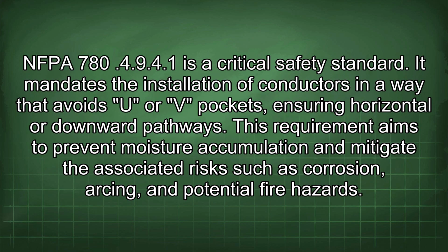NFPA 780.4.9.4.1 is a critical safety standard. It mandates the installation of conductors in a way that avoids U or V pockets, ensuring horizontal or downward pathways. This requirement aims to prevent moisture accumulation and mitigate the associated risks such as corrosion, arcing, and potential fire hazards.